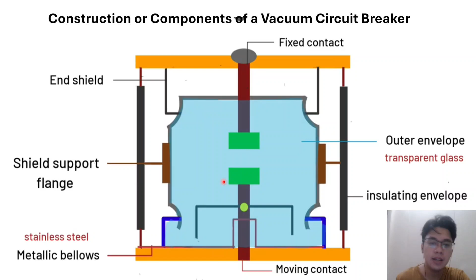The fixed and moving contacts carry current during normal operation. When a fault occurs, the moving contact separates from the fixed contact, and the vacuum inside the interrupter quickly extinguishes the arc, while the shields collect metal vapors and the insulating parts prevent electrical leakage. So at the same time, the metallic bellows allows movement while still maintaining the vacuum seal. Because of this coordinated design, the vacuum circuit breaker can interrupt fault currents safely, quickly, and efficiently.